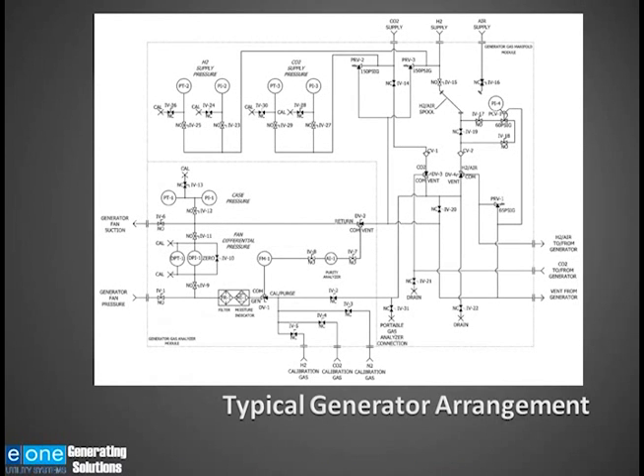This is a typical P&ID for the hydrogen auxiliary system. And I'm going to spend a few minutes talking about the various components in this system. On the top right-hand side, you can see where the supply CO2, hydrogen, and air is fed into the generator. Off to the left-hand side, we've got a pressure indicator for the CO2 supply pressure.